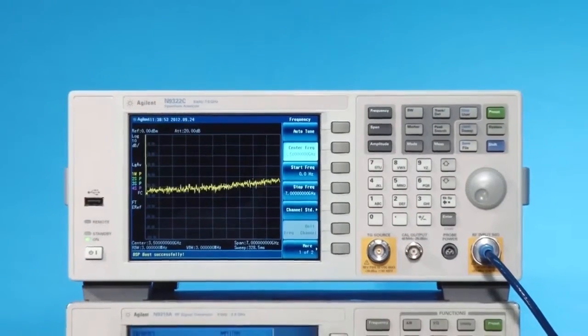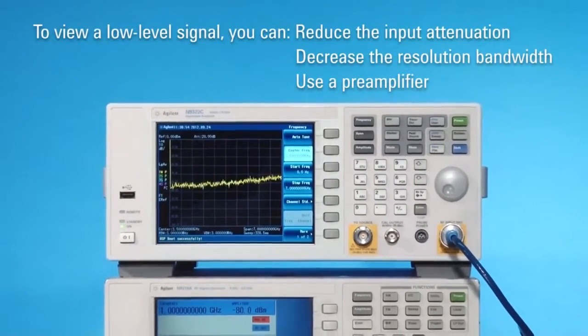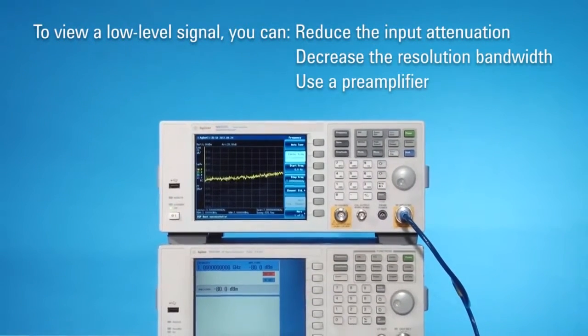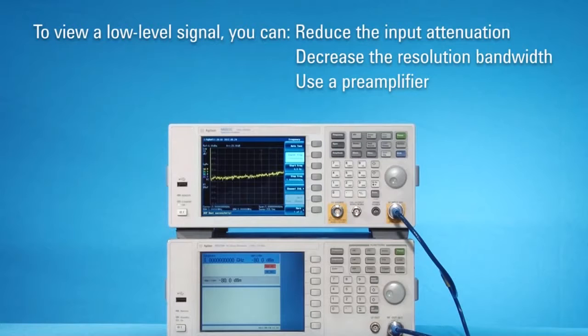And reveal the low-level signal: 1. Reduce input attenuation, 2. Decrease the resolution bandwidth, 3. Use a pre-amplifier.